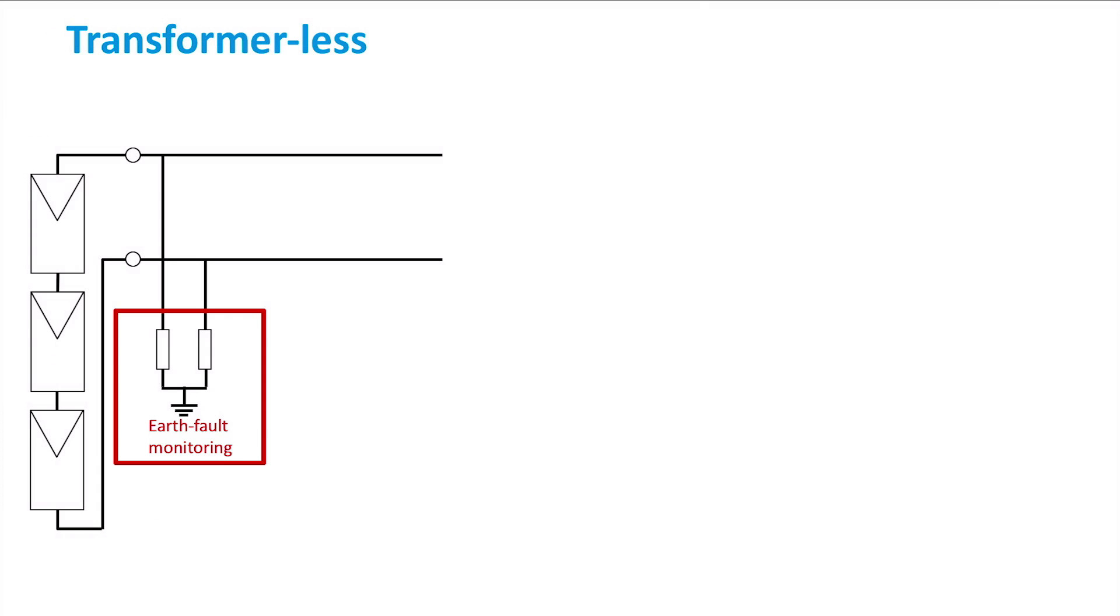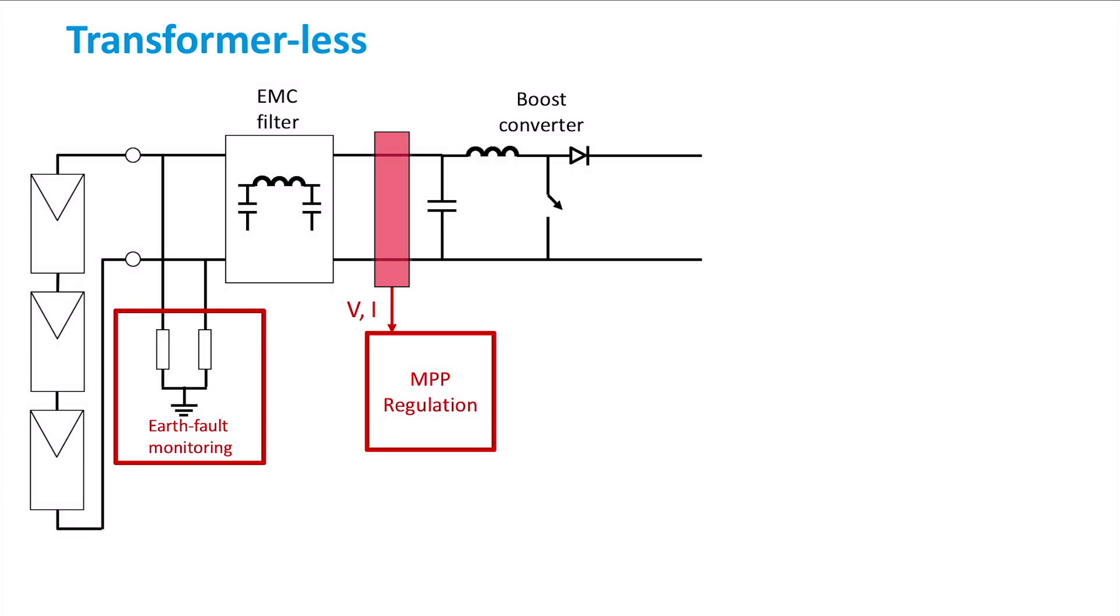An EMC filter is connected at the input of the inverter. EMC stands for electromagnetic compatibility, and it represents the ability of the electrical device to operate without being affected or causing electromagnetic interference. After the filter, current and voltage are measured and the data is sent to the maximum power point regulator. In order to keep the PV array at the maximum power point, a boost converter is provided.